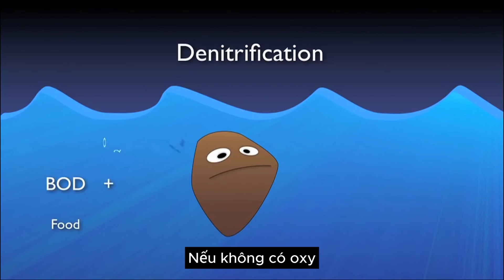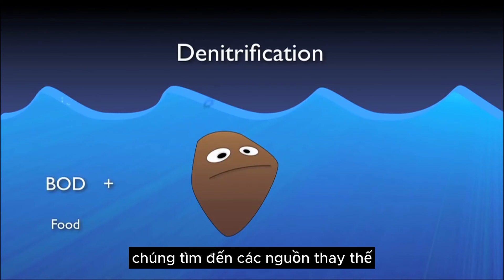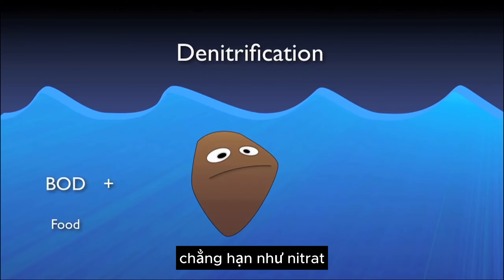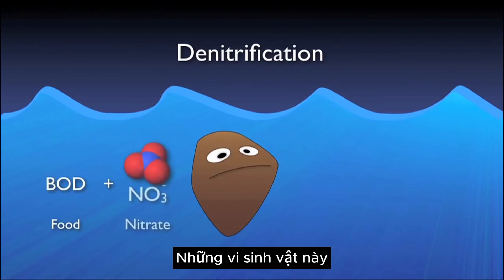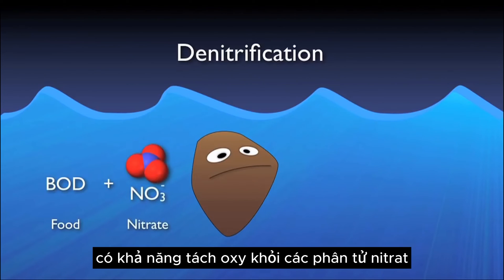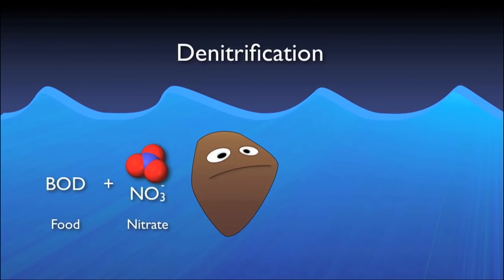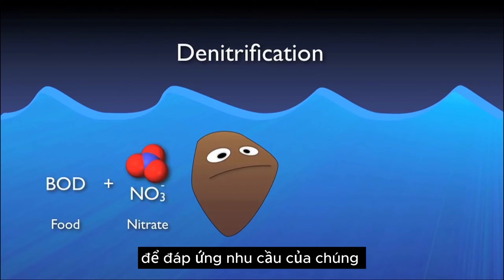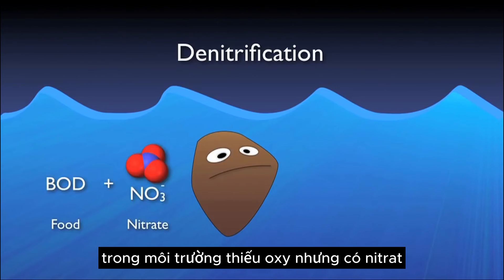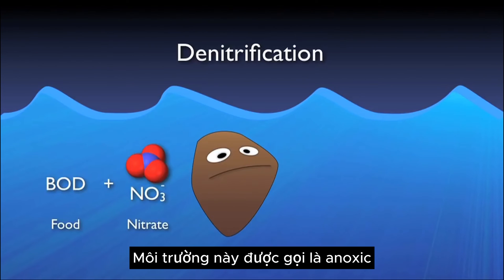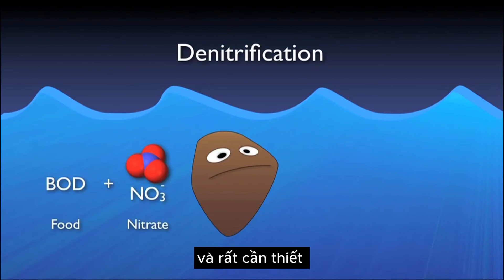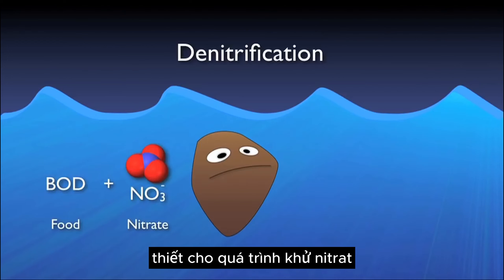If there is no DO present, however, they look to alternative sources, such as nitrate. These specialists have the ability to strip the oxygen from nitrate molecules to satisfy their needs. This critical environment where DO is not present, yet nitrates are, is referred to as anoxic, and is absolutely required for denitrification.